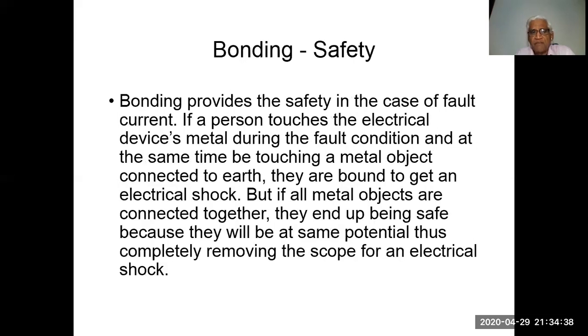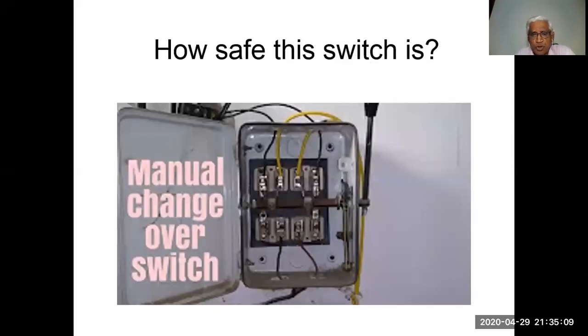Grounding does not impact the regular running of the electrical system. Bonding and safety. Bonding provides safety in the case of a fault current. If a person touches the electrical device's metal during the fault condition and at the same time is touching a metal object connected to the earth, they are bound to get an electrical shock. But if the metal objects are connected together, they end up being safe because they will be at the same potential, thus completely removing the scope for an electrical shock.